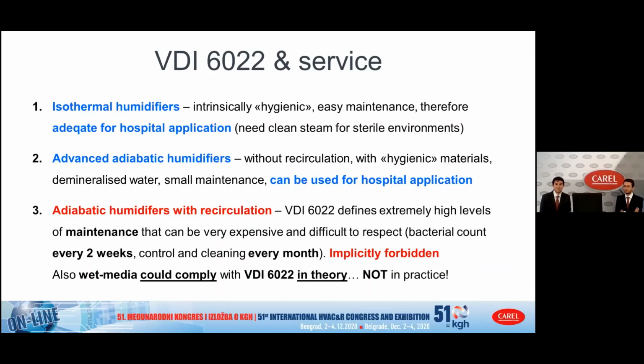Something that VDI implicitly says, but is not written in it, because it really depends on how you maintain humidifiers, is that if you want to use recirculation, or materials that are very good for bacterial growth, like porous materials, like paper or some kinds of plastics often used in wet media humidifiers, you must do very strict controls every 2 weeks or every month in order to ensure the humidification section and the air after the humidifier are clean and not risky for the patients or the people in the building.